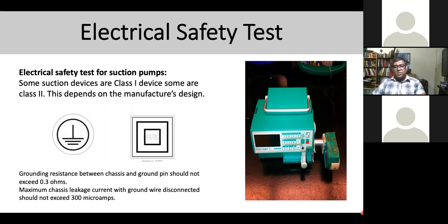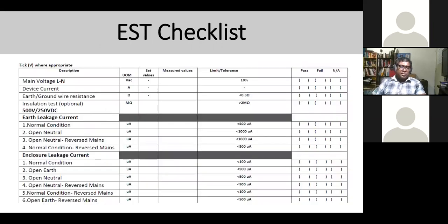This is the checklist you use to do electrical safety. So you've got mains voltage, device current, earth ground wire resistance, and earth leakage current. You've got all these particular measurements that need to be done using the electrical safety analyzer, and enclosure leakage current. These are according to IEC 60601 or 62353. So these are the standard checklists used to do electrical safety.